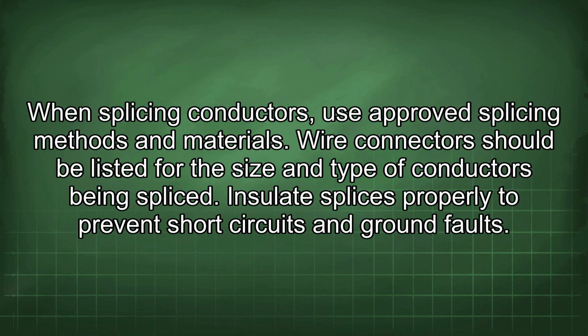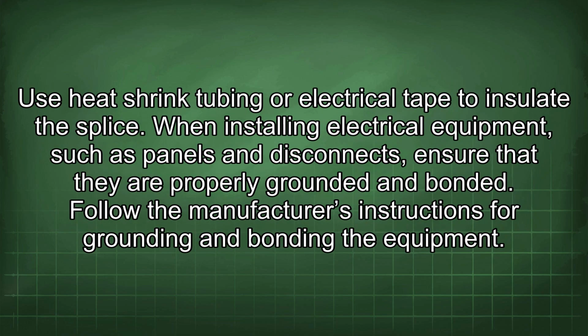When splicing conductors, use approved splicing methods and materials. Wire connectors should be listed for the size and type of conductors being spliced. Insulate splices properly to prevent short circuits and ground faults. Use heat-shrink tubing or electrical tape to insulate the splice.